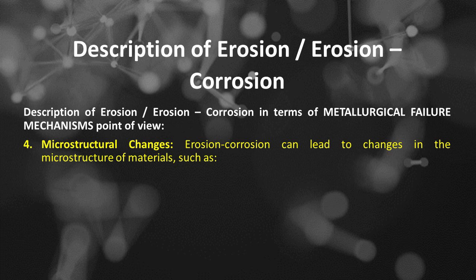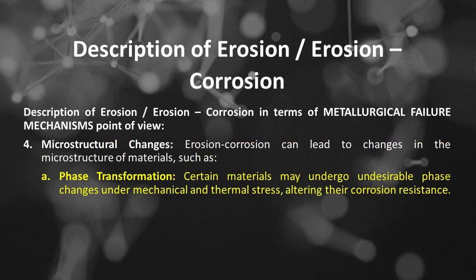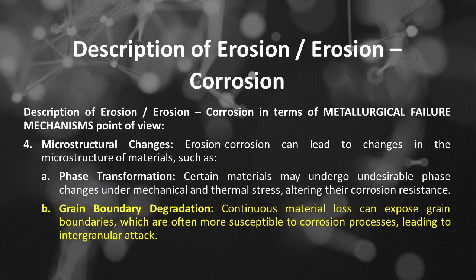Number 4 is microstructural changes. Erosion-corrosion can lead to changes in the microstructure of materials, such as: the first is phase transformation. Certain materials may undergo undesirable phase changes under mechanical and thermal stress, altering their corrosion resistance. The second is grain boundary degradation. Continuous material loss can expose grain boundaries, which are often more susceptible to corrosion processes, leading to intergranular attack.